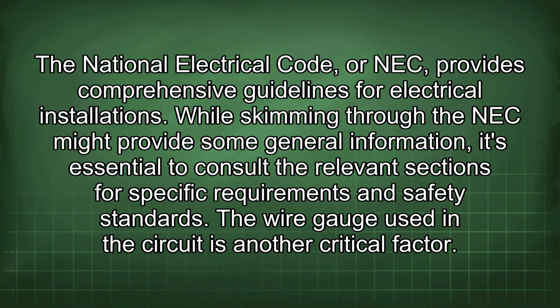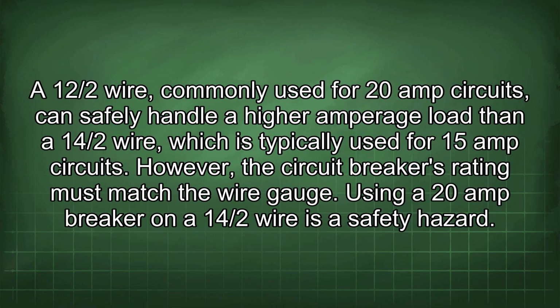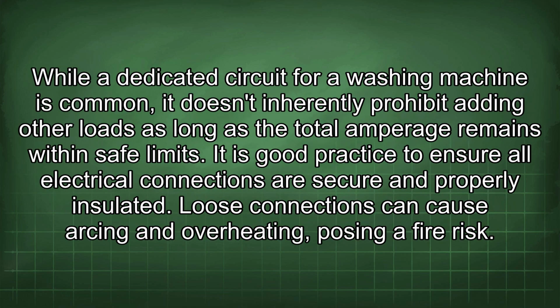While skimming through the NEC might provide some general information, it's essential to consult the relevant sections for specific requirements and safety standards. The wire gauge used in the circuit is another critical factor. A 12/2 wire, commonly used for 20 amp circuits, can safely handle a higher amperage load than a 14/2 wire, which is typically used for 15 amp circuits. However, the circuit breaker's rating must match the wire gauge. Using a 20 amp breaker on a 14/2 wire is a safety hazard. While a dedicated circuit for a washing machine is common, it doesn't inherently prohibit adding other loads as long as the total amperage remains within safe limits.